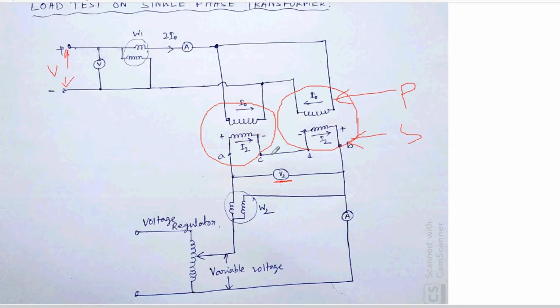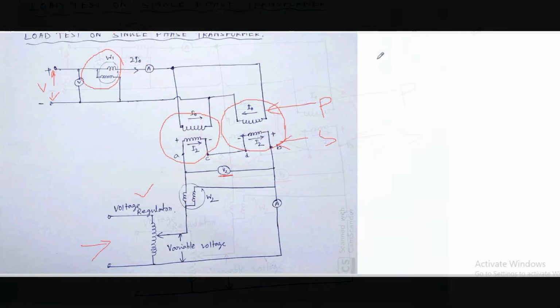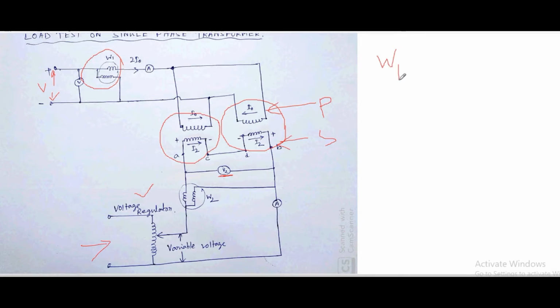Now here we have a voltage regulator, and by this voltage regulator we can inject a voltage into this secondary. When the secondary is open, this wattmeter W1 will show the no load power, and no load power means core loss. So W1 will show the core loss.